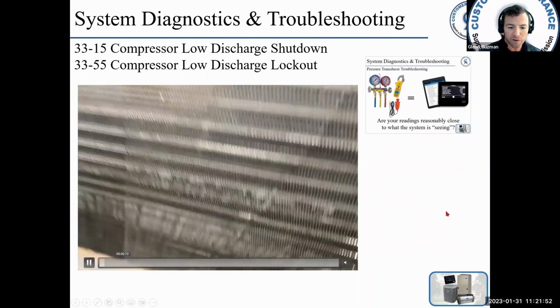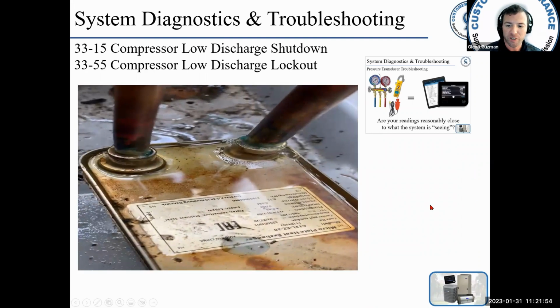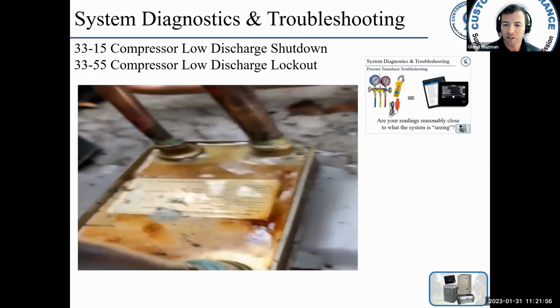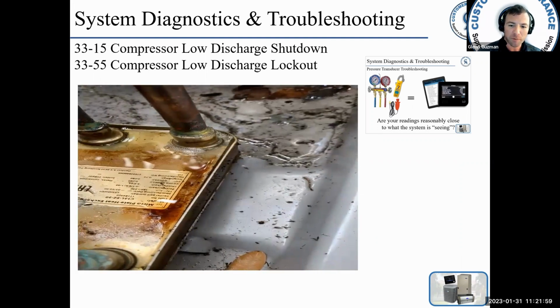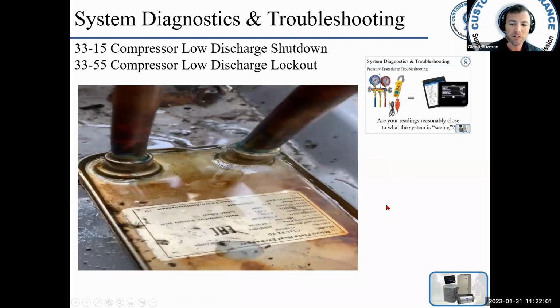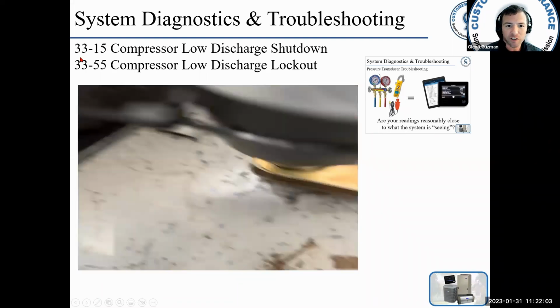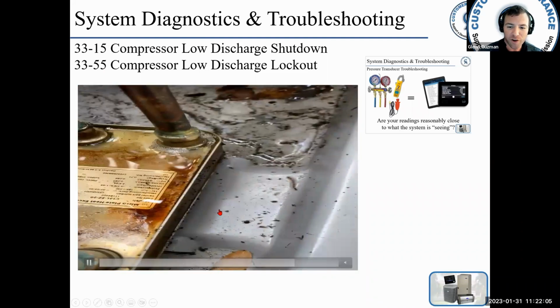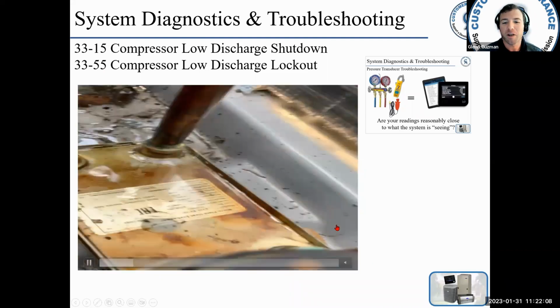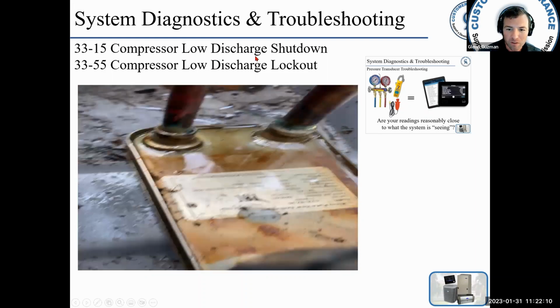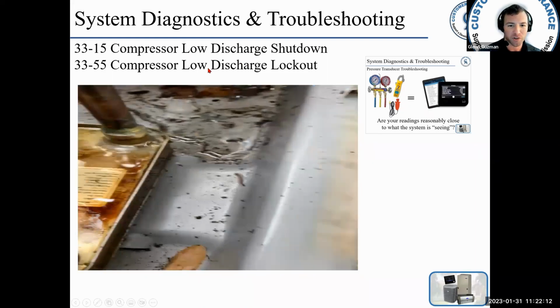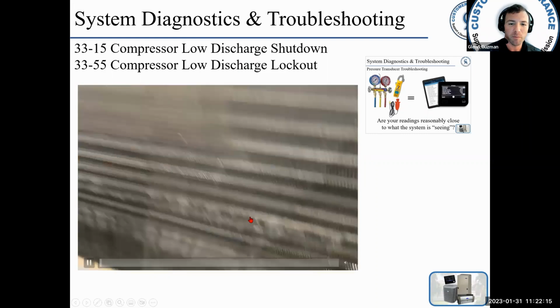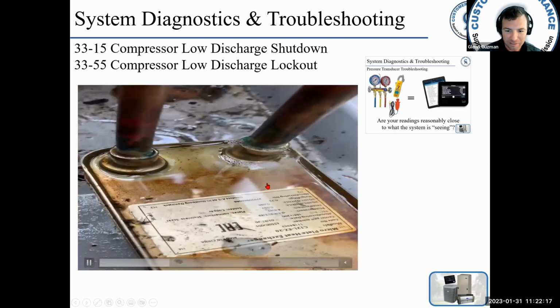3315 low discharge shutdown, and 3355 the lockout. Okay, I'll show you a video here. You can see clearly a leak. You can see the bubbles on the braze plate heat exchanger. Now, I'm not saying you'll get these faults if you have a leak on the braze plate heat exchanger, but any leak in general, okay, low discharge pressure you can get from a leaking component inside the system, okay?